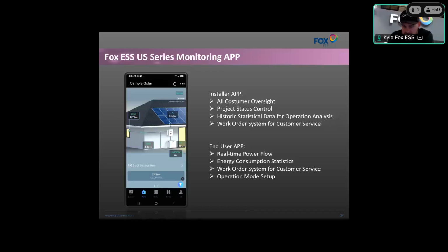So it monitors the state of charge. When it gets down to 30% or 20%, the generator kicks on until it gets back up to 80 or 90%, then kicks the generator back off. Some people leave the generator running at night so batteries recharge in the morning, then run off the batteries. But if you're putting this much money into a nice system, my recommendation is to tie it into our system, because we can monitor not only your battery level but your entire household and minimize generator use. Nobody wants to listen to their generator at night.